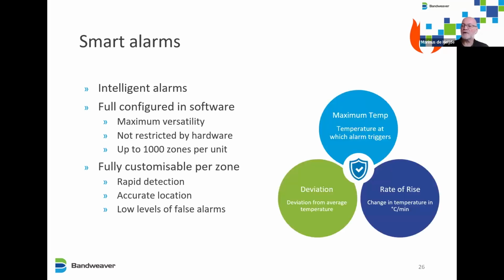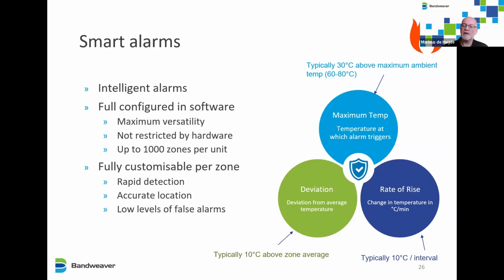So what we've got: we've got a maximum temperature alarm. It's typically 30 degrees above the maximum ambient temperature, so temperature is normally set at 60 to 80 degrees. We've got a rate of rise alarm, typically around 10 degrees per minute. But as we will see in some of the case studies, people also set them at a lower level to get a quicker alarm. And then last of all, we've got a deviation alarm, which is again typically set 10 degrees above the zone average.